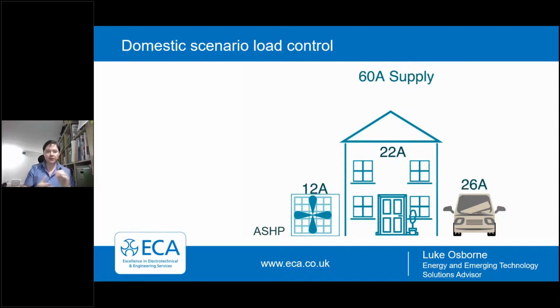So this works by smart monitoring, monitoring the availability. It sets the availability that's coming into the property. It will monitor the loads of the building. It could monitor the entire loads or specific loads like the air source heat pump, which is going to be a heavy demand, and also the outgoing to the vehicle. So it cleverly balances everything, and that ensures that you will never go above the demand that's being placed onto the property.